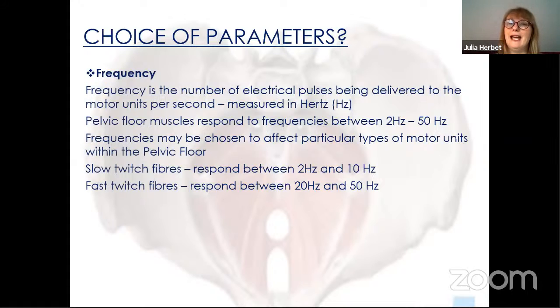So frequency is how many electrical pulses are being delivered to the motor units per second, and we measure it in hertz, Hz. And for the pelvic floor, it will respond between 2 hertz and 50 hertz. You could put a higher frequency in there, because once you get beyond a particular frequency, the muscles that respond at lower frequencies will be getting sufficient stimulation to make them respond and stay contracted. But there's no need to load the delicate pelvic area, particularly of men and women, with higher energy than we actually need. So the pelvic floor doesn't need any more than 50 hertz to get all the muscle fibers reacting and staying in a summated contraction.